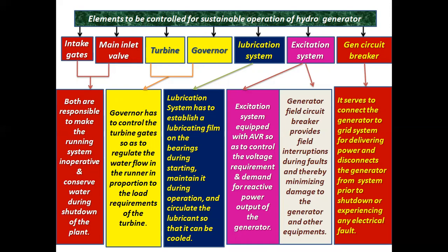Now, intake gates and main inlet valve are both associated with the following points. Both are responsible for making the running system inoperative and conserving water during shutdown of the plant. Turbine and the governor: the governor has to control the turbine gates so as to regulate the water flow in the runner in proportion to the load requirements of the turbine. The lubrication system has to establish a lubricating film on the bearings during starting, maintain it during operation, and circulate the lubricant so that it can be cooled.